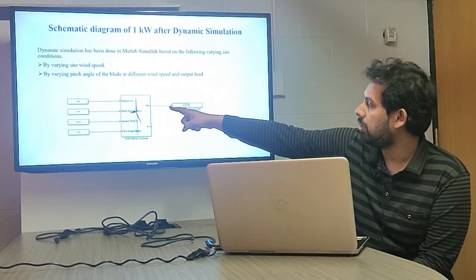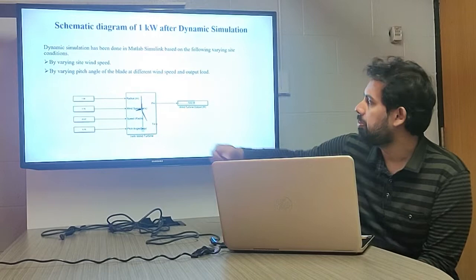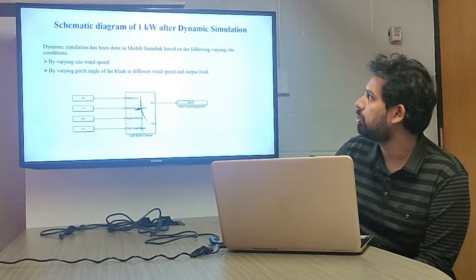When the blade radius is 1.98 meters, wind speed is 7.78 meters per second, angular speed is 25.07 radians per second, and pitch angle is 0.75, we got an output of 533.9 watts. By varying these input variables we get different outputs, which is what we demonstrated in MATLAB Simulink.